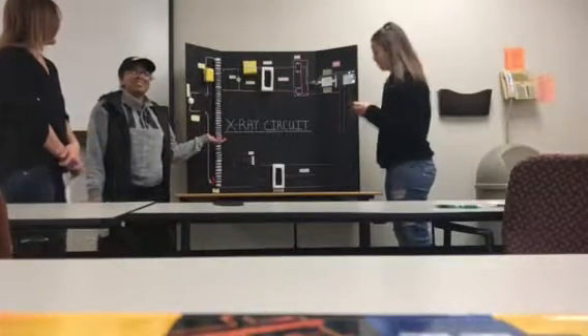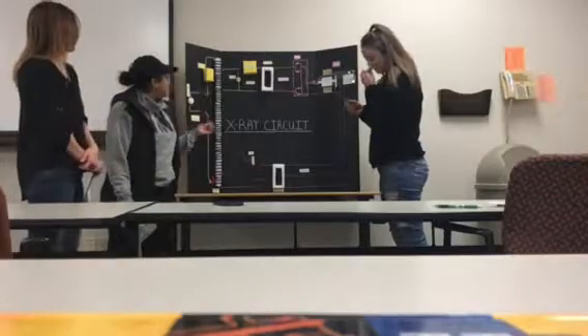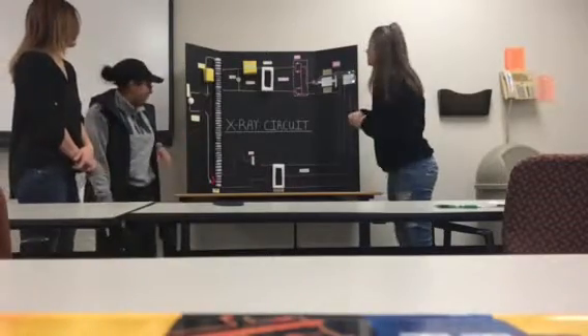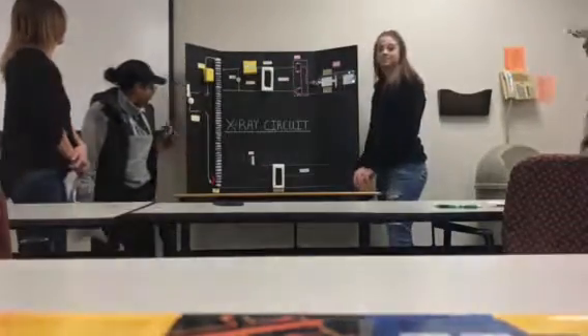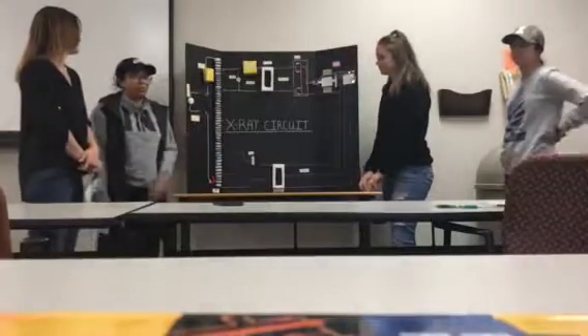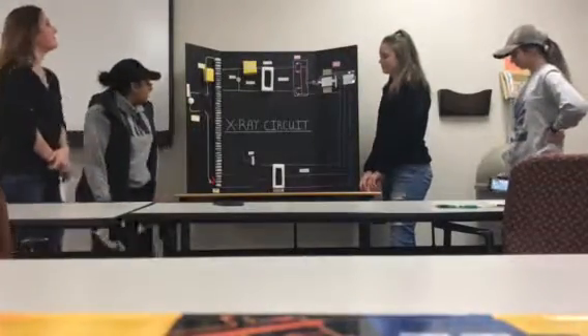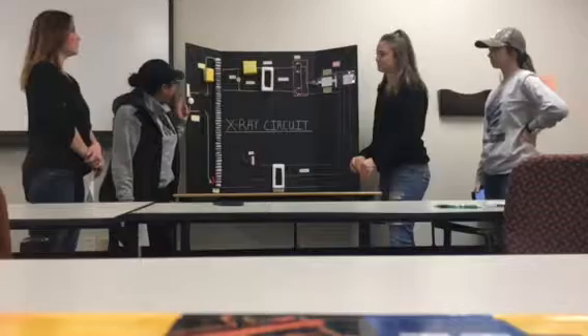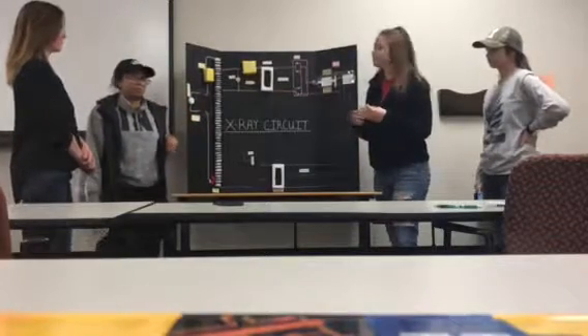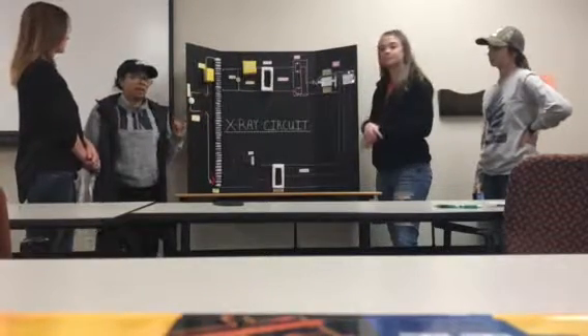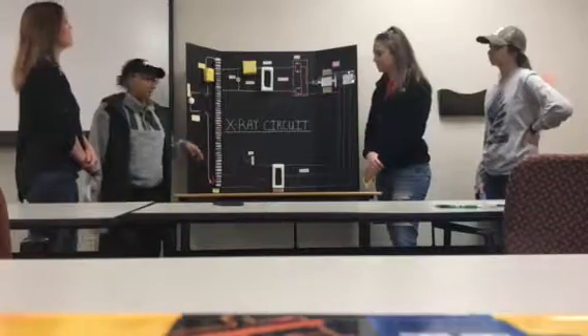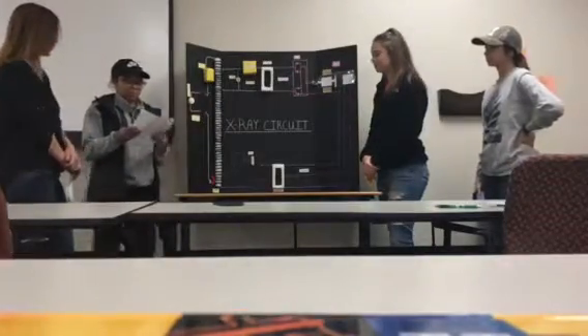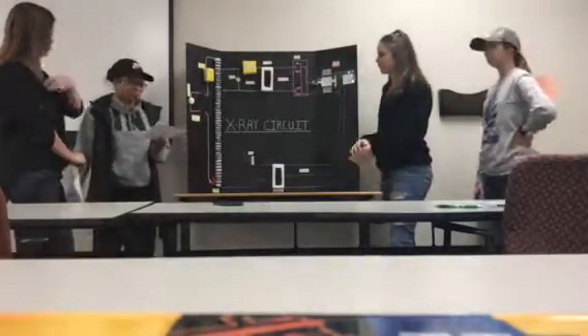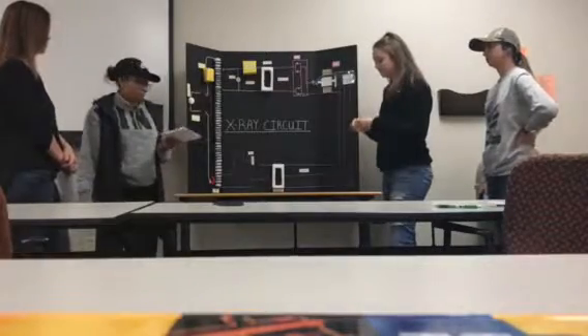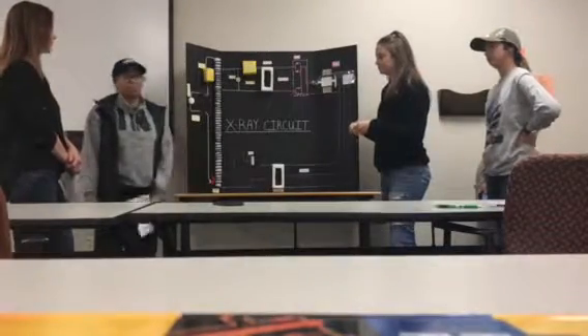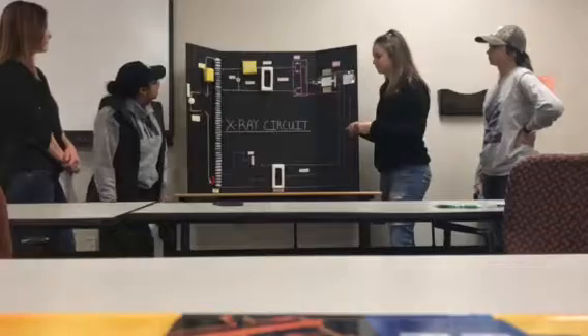This is our X-ray circuit model. Me and Bree will be talking about the primary circuit. The main power switch just simply turns the power supply on and off. And then the incoming power supply needs to be a consistent 220 volts, and at first it's not. So that's why there are line compensators, and the line compensators are wired to the auto transformer, which will automatically adjust the power supply to the X-ray machine to 220 volts.